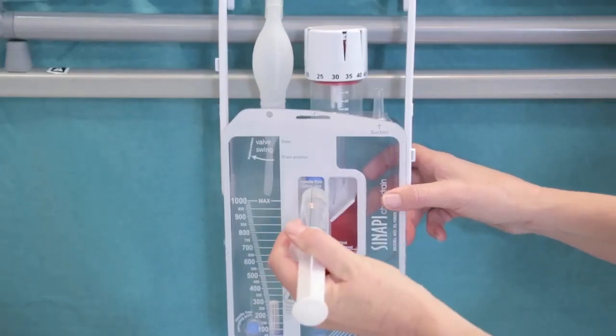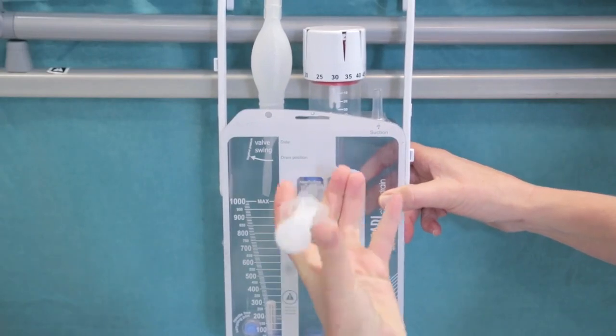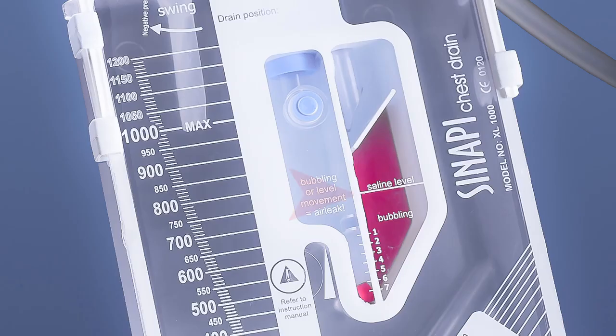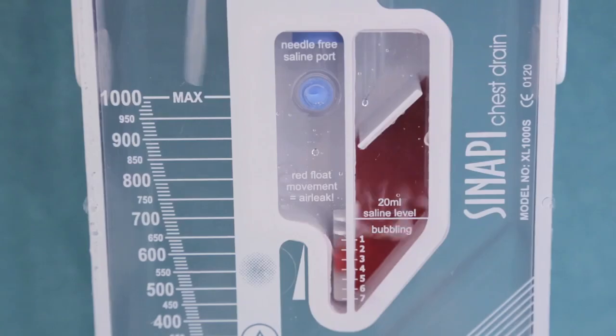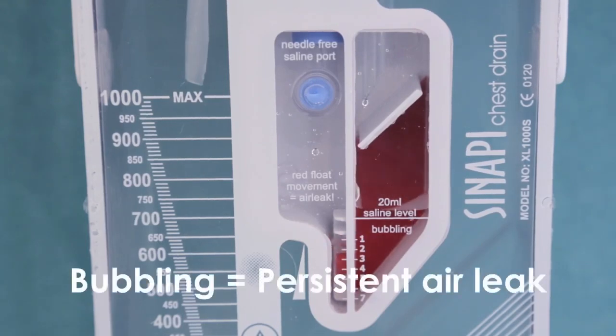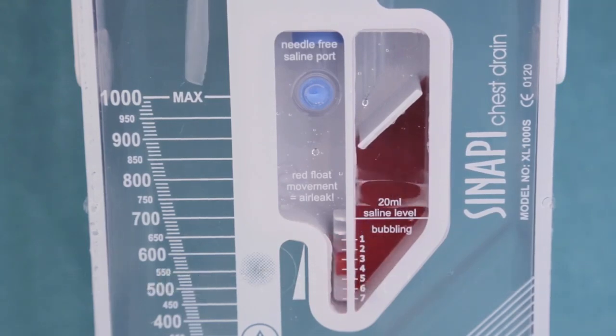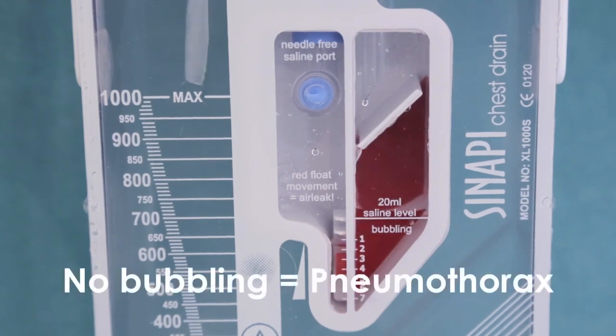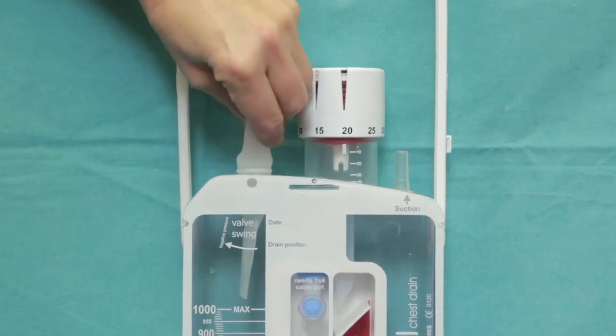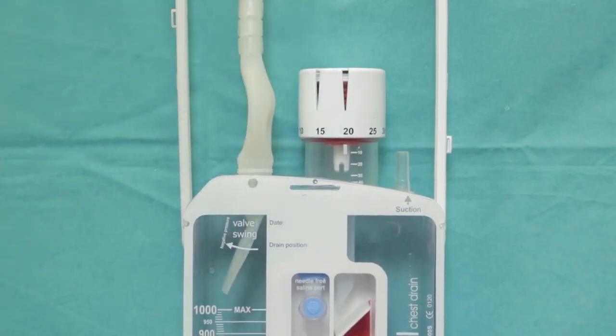To verify a persistent air leak, fill the air leak chamber by administering 20 milliliters saline through the needle-free sampling port. Look for bubbles. If bubbling is visible, air is evacuating from the chest, indicating a persistent air leak. If bubbling is not visible, air is not evacuating, but a pneumothorax still exists. The pneumothorax is only resolved when the bulb does not re-expand after being manually depressed.